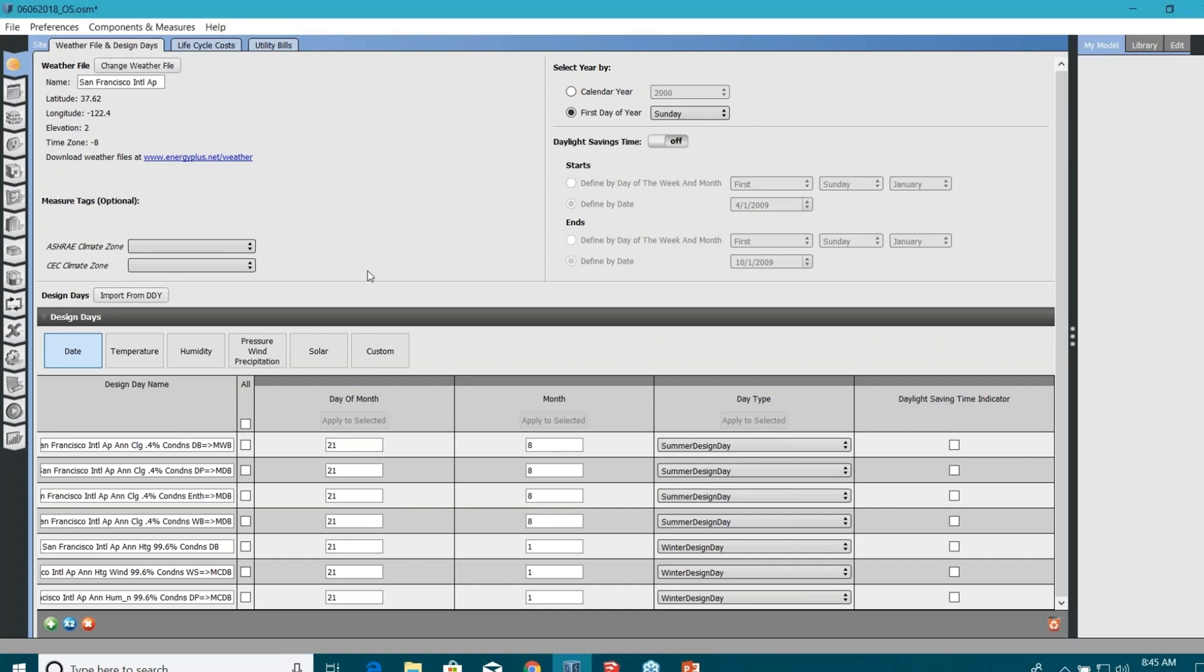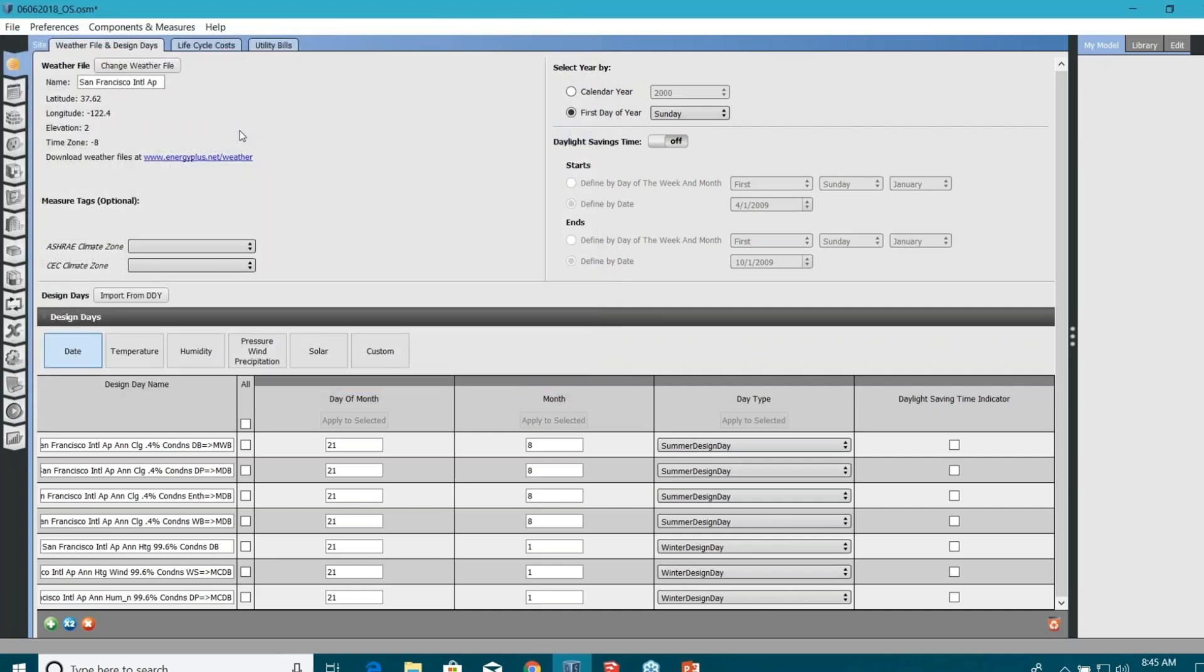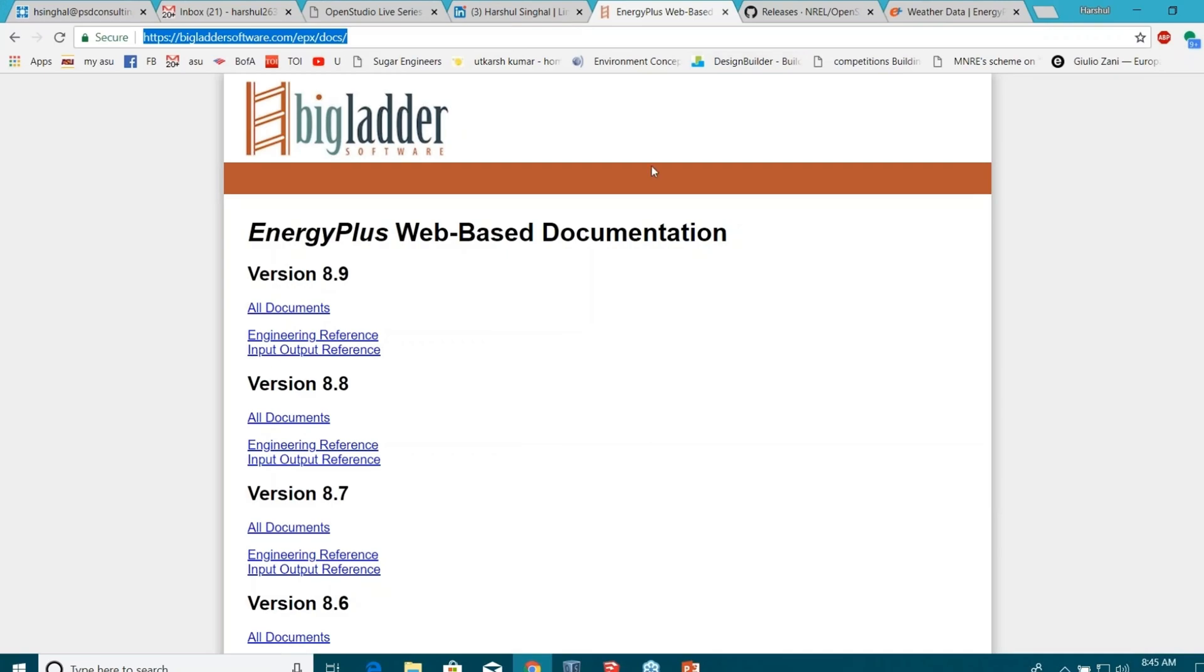Let me explain you what a design day file is. When you auto-size your HVAC systems, you have to provide a design day weather file. Either you can hard size your systems, provide a capacity of let's say 100,000 kBTU per hour boiler or something, or you can ask your software to do the auto sizing for you. That's what you do for your ASHRAE 90.1 baseline models. In case you need to do auto sizing, you just need to provide the design day file. Click on it. In case you want to read more on them, you can just go back to the Energy Plus documentation and look into it. It gives you more information.